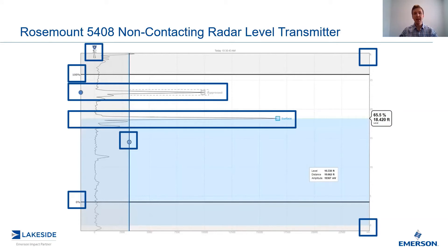Next, we have a blue vertical line. This is the threshold to which we ignore background noise — it can be dragged sideways based on the level of noise we have. Everything below it will be suppressed. We can also split the line and draw different shapes depending on different noise levels we see. So if we happen to see higher noise levels near the top of the vessel, you can draw that L-shape to ignore those accordingly.